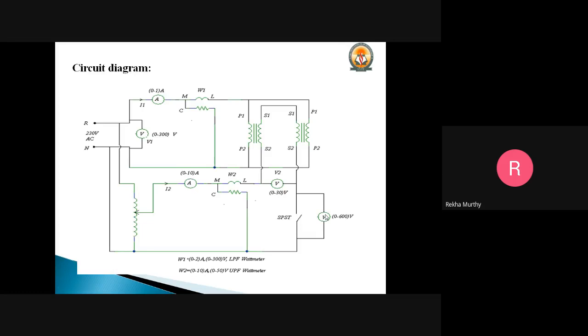If the voltmeter reads 0, then we can close the SPST switch and conduct the experiment. If the voltmeter indicates twice the secondary voltage, then the secondary terminals of any one of the transformers will be interchanged, to make the voltmeter read 0. Only then is the SPST switch closed. So we have to ensure that this voltmeter reads 0 when the SPST switch is open. If it is reading twice the voltage, then we have to switch off the supply and interchange the connections of the secondary windings.